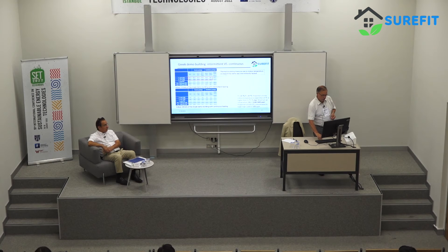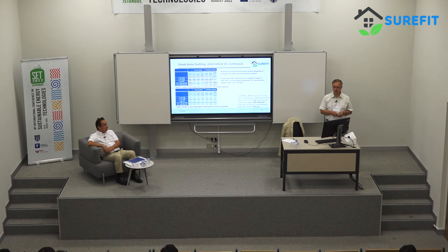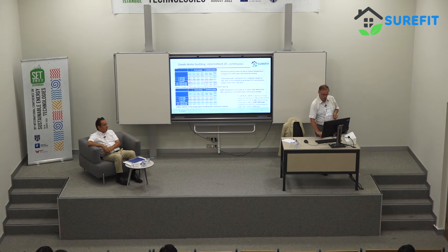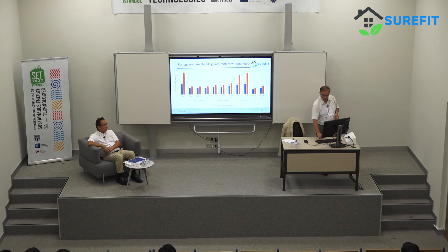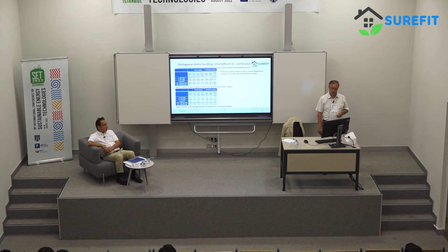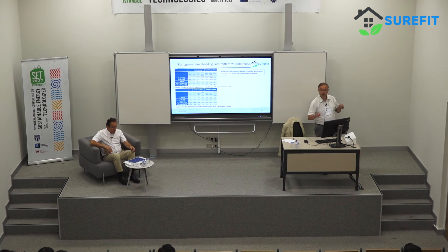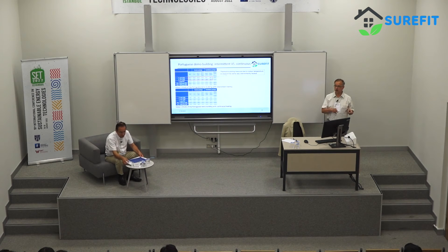The RAHU here means room-specific air handling unit — that's implemented there, and it's one of the novel technologies introduced in the SureFit project. In continuous heating the efficiency impact on thermal comfort is less pronounced. Results across different countries are quite similar, with slightly different numbers. We do show improvement in conditions, but with intermittent heating room temperatures are still not ideal — if you look at European standard Class A, this target is not exactly fulfilled because heating is used intermittently.